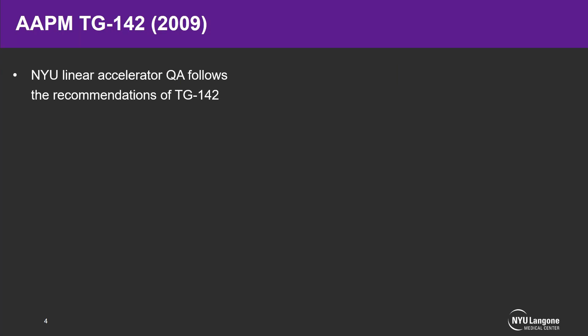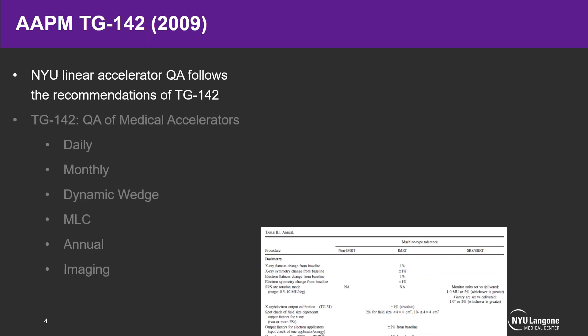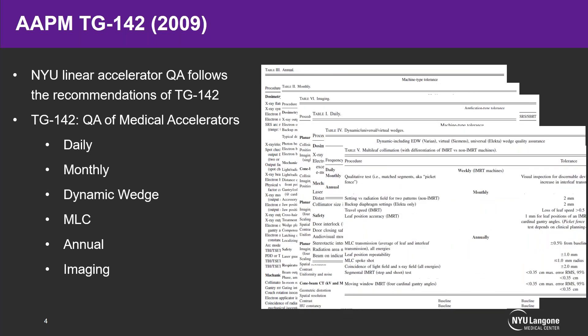I want to refresh everyone on AAPM TG142. The NYU Linear Accelerator Program follows the recommendations of TG142. The QA recommendations are spread over six different tables: daily, monthly, dynamic wedge, MLC, annual, and imaging. Each provides a procedure, tolerance, baseline, and frequency, and they are all dependent on whether you're treating with an SBRT or non-SBRT machine. Overall, there are 100 plus tasks over these six tables, so it's quite a bit to manage and keep on top of.